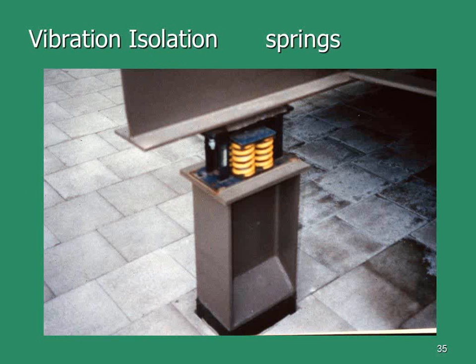Because when we actually go above the drop ceiling, the tile ceiling, up in that space you hear no noise. You come down into the classroom and you can just feel the pulse and hear the noise. It's sort of odd—you go up above the ceiling tile and it's a metal roof, mounted with no isolation pad on the roof, and you really don't hear the vibration. But when you put the tile back in, you hear the vibration.